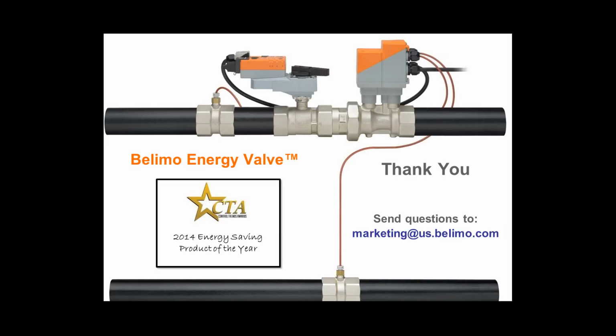Only when we violate the delta T threshold. So like all day, every day in a well-designed building, the delta T manager theoretically wouldn't come on. The only time it ignores the automation system is when we're in violation of that delta T threshold. So we set it at 12 and it's running at 12, or 12 and a half, or 14, or whatever. We're totally listening to everything that the automation system's asking for.